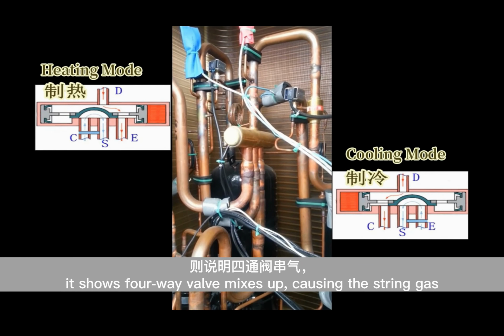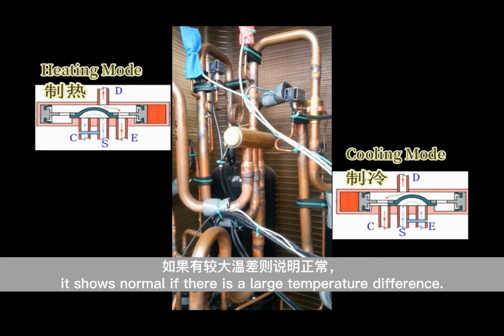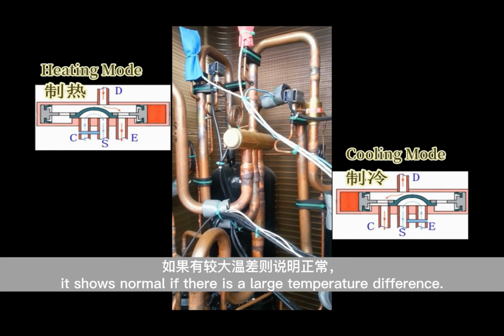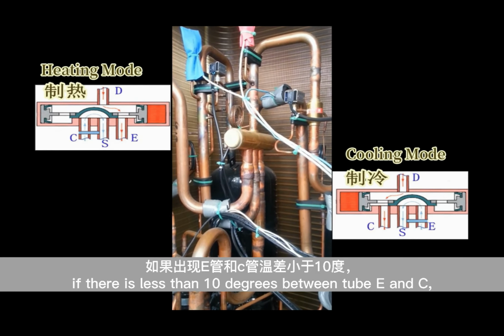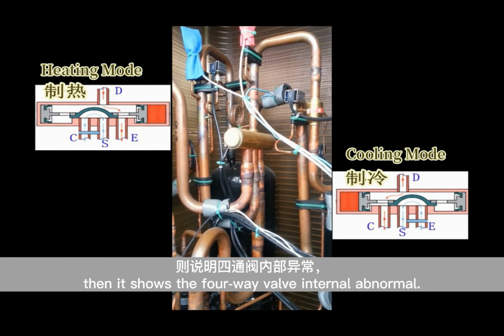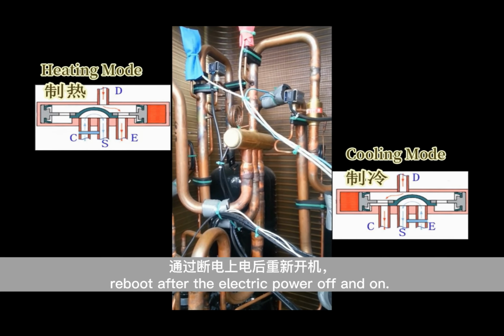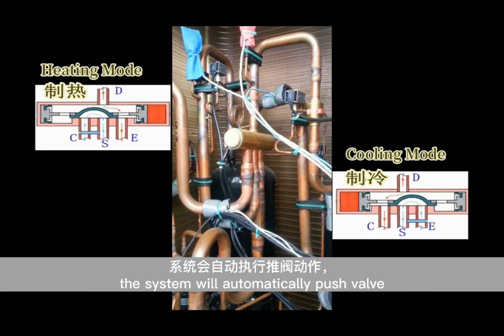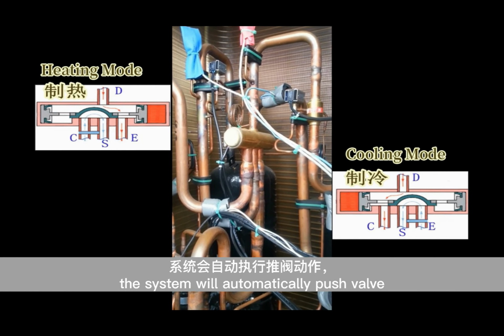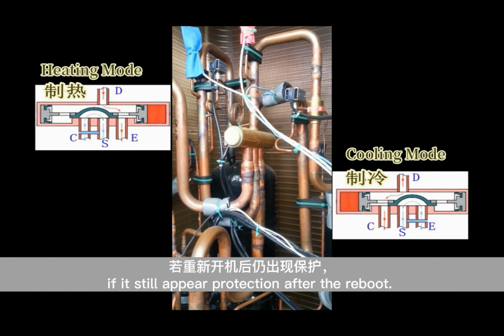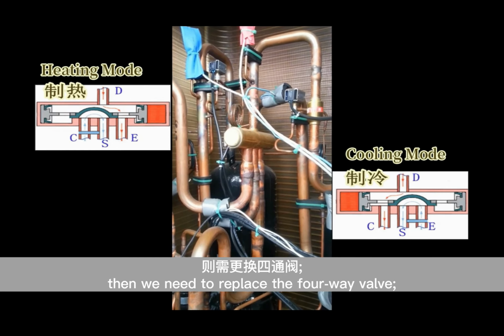causing the string gas. It shows normal if there is a large temperature difference. If there is less than 10 degrees between tube E and C, then it shows the four-way valve is internally abnormal. Reboot after the electric power is off and on. The system will automatically push the valve. If the protection still appears after the reboot, then we need to replace the four-way valve.